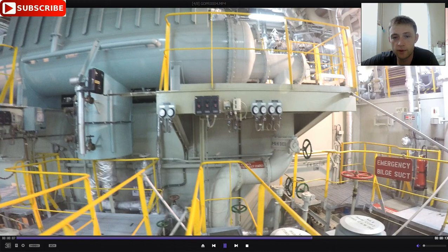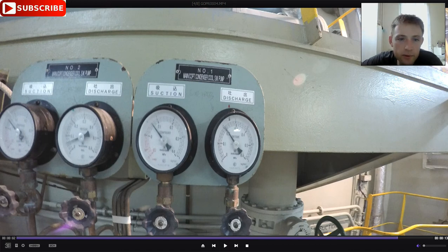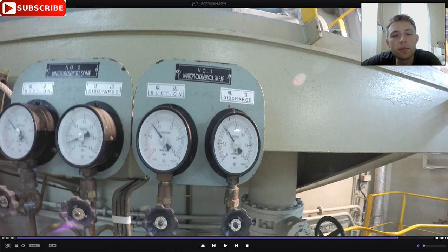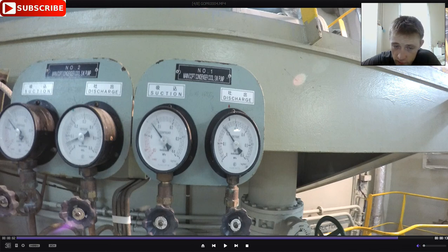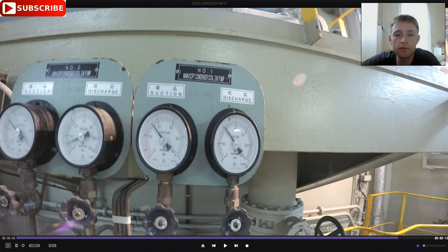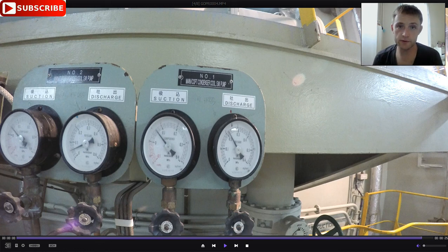This is the cooling. This is the number one main condenser cooling sea water pump. Here you can see the suction is 0.6 bar, and the discharge is 2 bar — about 20 meters head of water. That's about the main condenser. Thank you for watching, bye-bye.